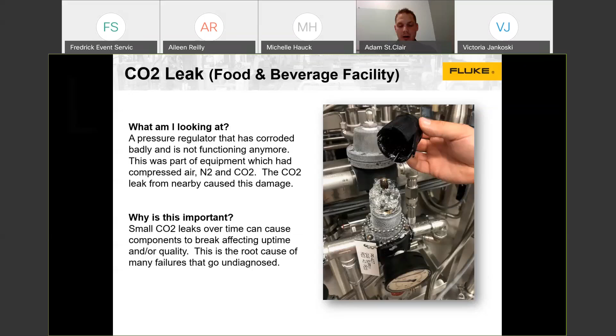And so again, out of curiosity, we took the acoustic imaging technology out there, did a scan and got a sound map. And what we found was that there was a CO2 leak right next to this pressure regulator, and that off-gassing of the CO2 was causing that corrosion. So the root cause was not a faulty pressure regulator or anything wrong with the install. It was that CO2 leak right next to that regulator that was continuing to cause them to fail, and changing out the regulators wasn't going to do anything. Every one they put in there was going to continue to fail until they fixed that root cause by tightening up that CO2 leak. So again, just a neat example of getting to root cause and having it be something that was really off the radar of anybody that was trying to work the problem.